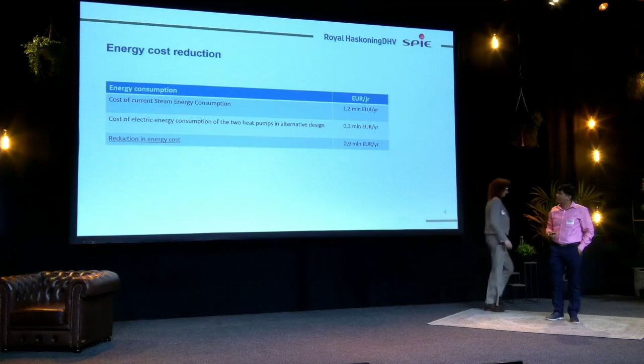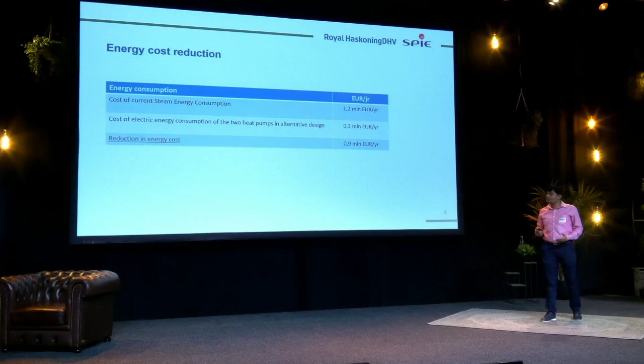Now we will go to the cost perspective of this case study. We calculated that steam is imported at an average of 5.5 tons per hour, which currently requires 1.2 million euros per year based on steam energy consumption. As explained, for the alternative case with the smaller heat pumps, we only need electric energy, calculated at around 0.3 million euros. So there is a lot of cost reduction, around 0.9 million euros per year. Now we will go to the investment.